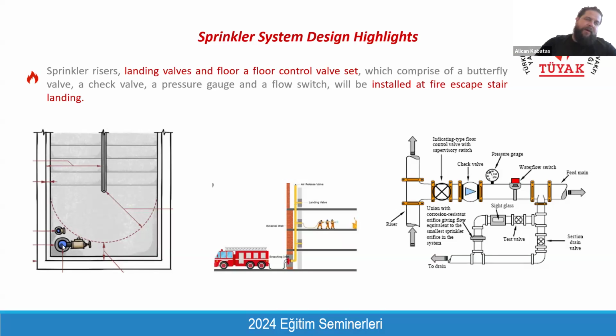But when you are locating this equipment, these pipes and risers within the fire escape stairs, you should pay attention that these should not be located within the clear width of the staircase. This is the stair circle and stair semicircle, and all of this equipment should be located outside of this required width. This is very important. Otherwise, you probably will have some troubles with the local fire brigade during the acceptance phase. That's why you need to ask the MEP contractor, the MEP designer, how many pipes will be located within the staircase and how many reservations they are requiring, so that you can determine the required width of your landing. It probably will be larger than required, but these areas will be used for MEP installation.